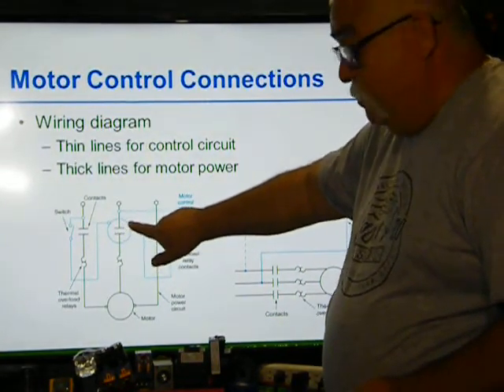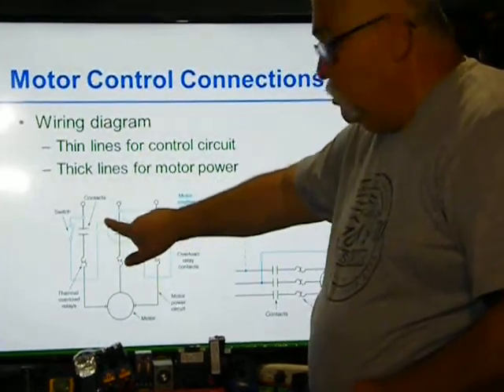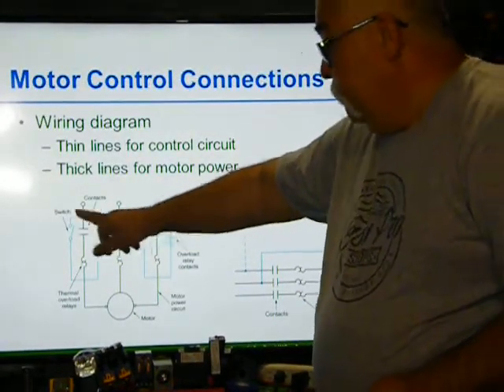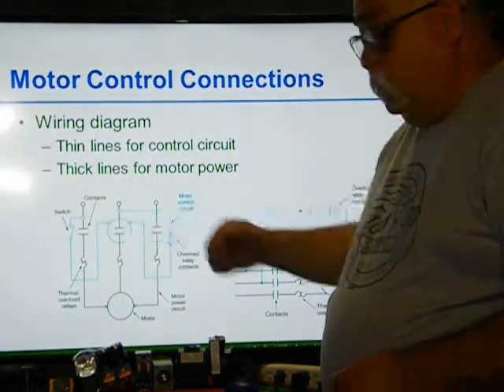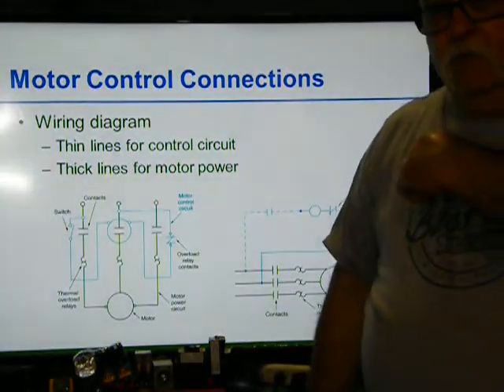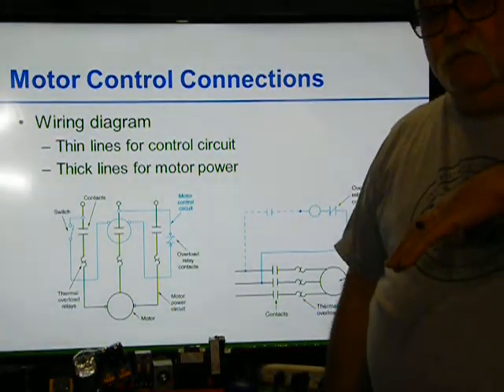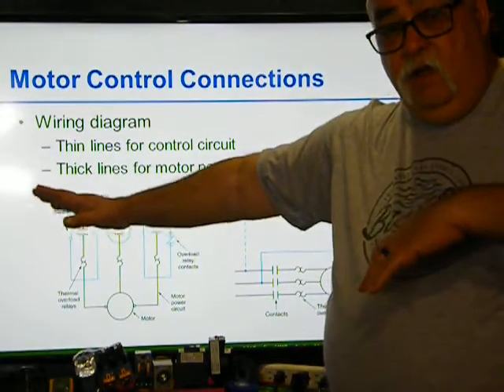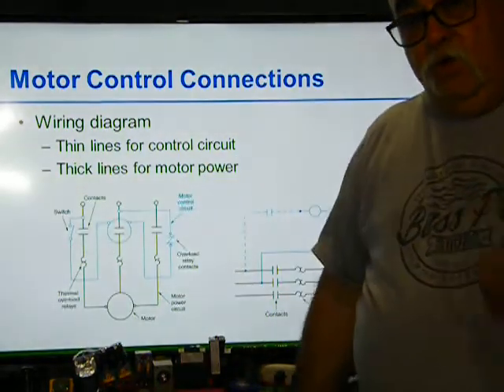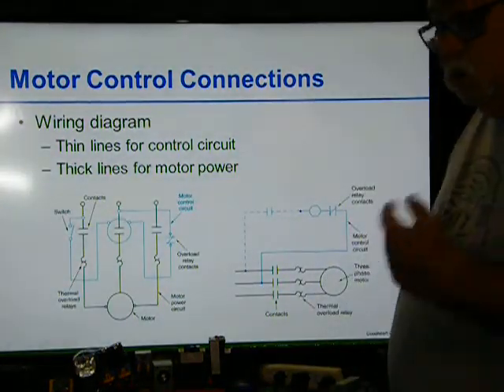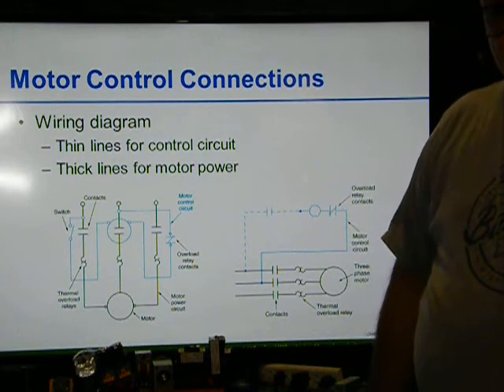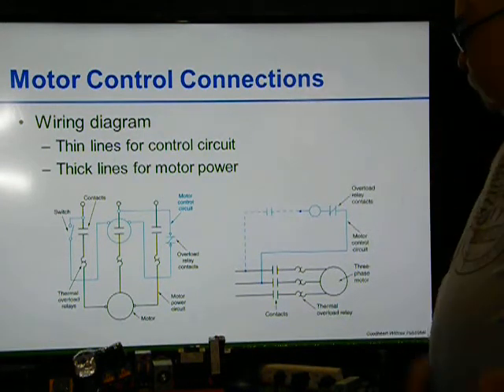The coil. This one would be hot here all the time. This is just waiting, it's hot. I close that switch. That gets hot. This motor comes on. Okay. The only problem with this is power goes off, and that switch is in the on position, or the closed position. Okay. What's going to happen? That motor's going to come right back on. So you have to be careful with that.